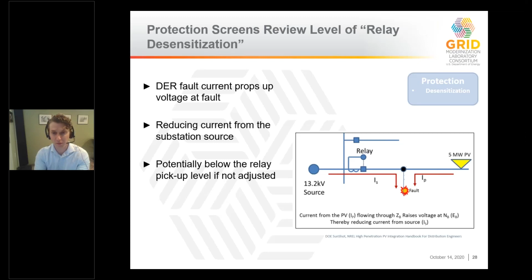There's this concept of relays being desensitized, the inability of the utility's relay to detect an issue on the system. When DER feeds a fault, such as a tree falling on the line, and both the utility system and the DER are feeding that fault, this can lead to desensitization. It's important for safety and reliability that utility relays can detect faults and quickly isolate the problem. If DER prevents that ability, that's an issue hosting capacity screens for.